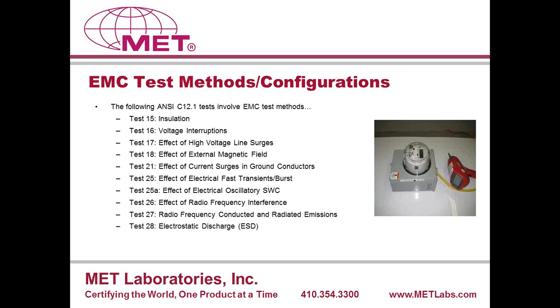Now, some of the tests that are different in the ANSI C12 standard are the test 18, effect of external magnetic field. So basically, this test is not at all similar to the magnetic field test that is performed under 61000-4-8, where you immerse a product into a magnetic field. But what the ANSI test calls out for is we have to use a 6 feet by 6 feet conductor and generate 100 amps of current into this conductor. You then place your meter within close proximity to this coil. You place it 10 inches from this coil, and then you basically test the effect of magnetic field on your meter using the proximity test method. So that is something that's different here in ANSI, and it's partially unique because no other international standards require you to test this way.